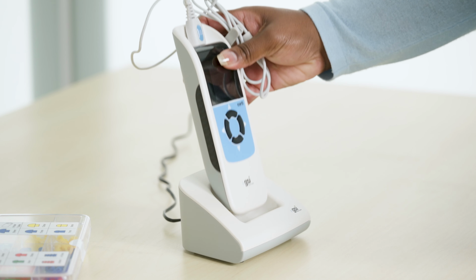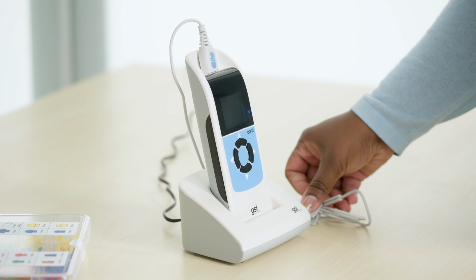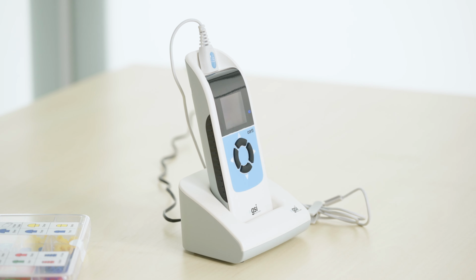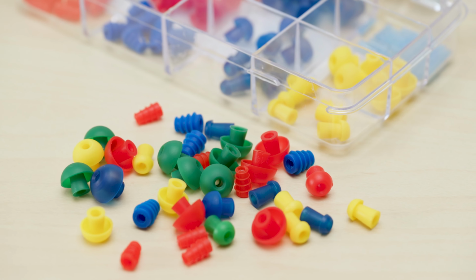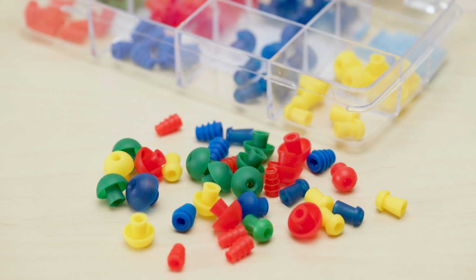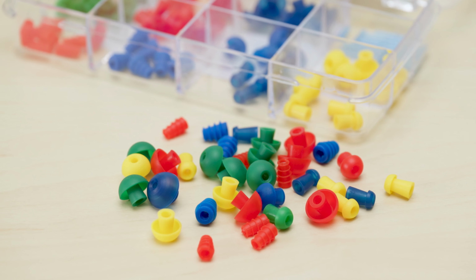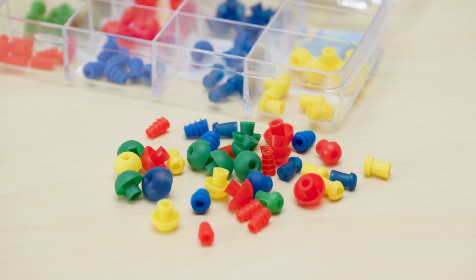When you first arrive at the screening venue, put the GSI Corti device into the charging cradle and be sure there's adequate battery power. Take a close look at the end of the probe and make sure the tiny tubes or ports are all clear. Also, be sure you have a good supply of different sizes and colors of clean silicone ear tips.